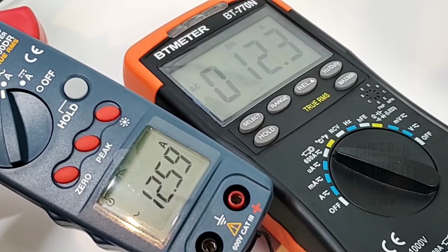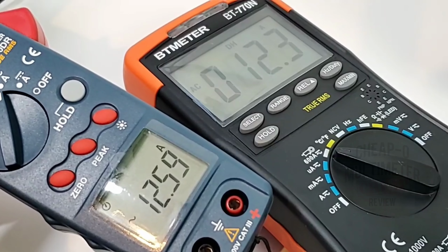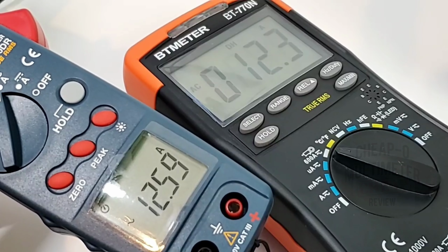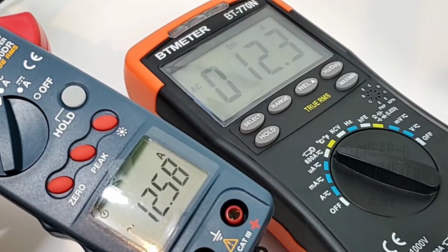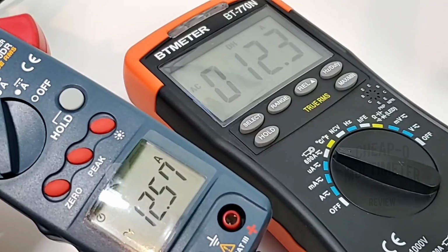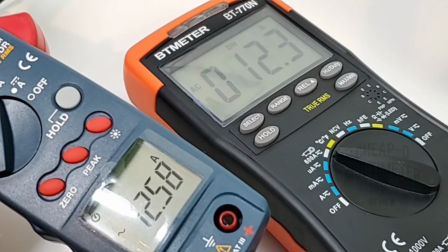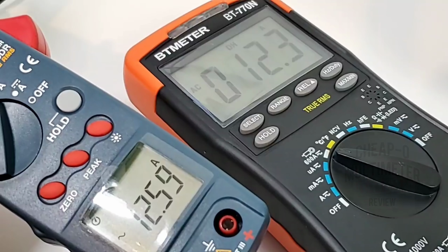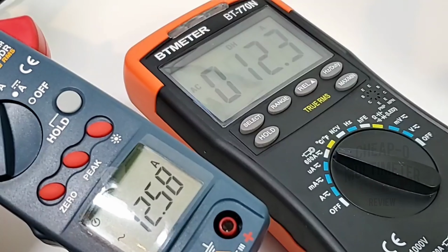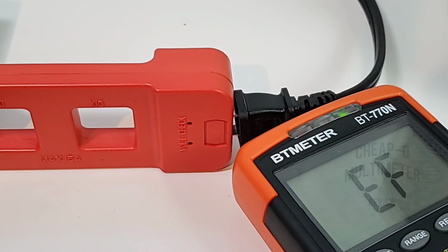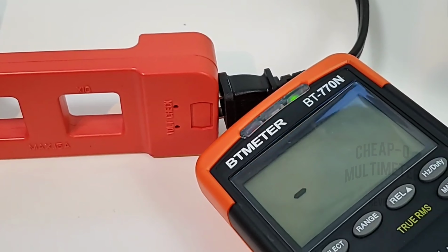Here's a Sanwa clamp hooked up to the same splitter, and it's coming in at around 12.5 amps or so. Pretty darn close for the BT-770N. All things considered, it is not a clamp meter per se, but with that optional accessory, you can turn it into one. Neat. Checking out the NCV feature, non-contact voltage, right now.